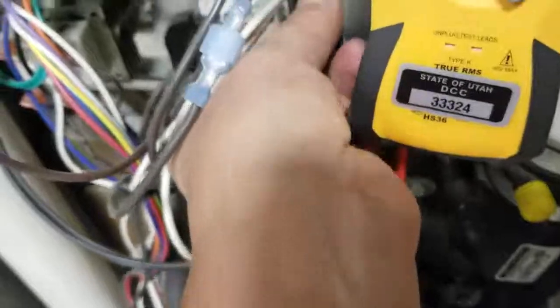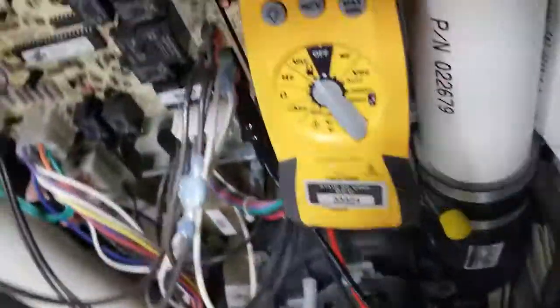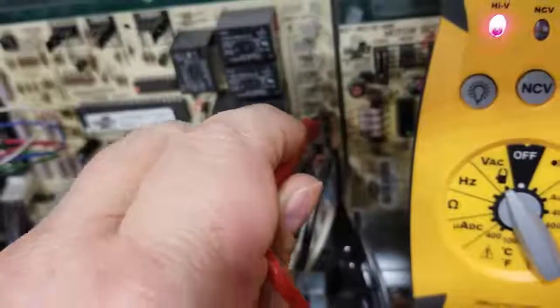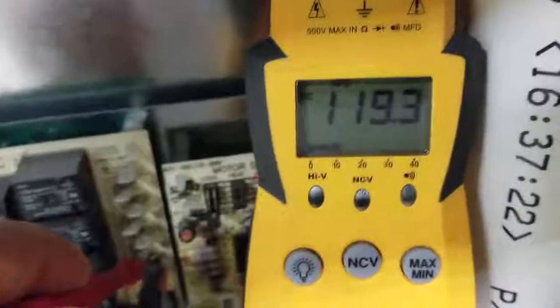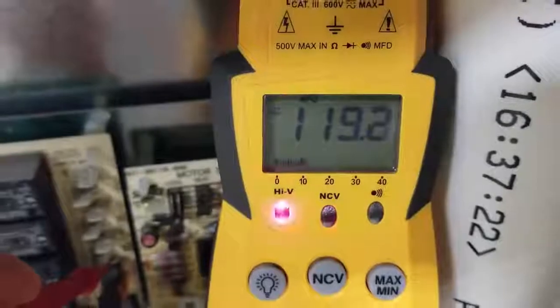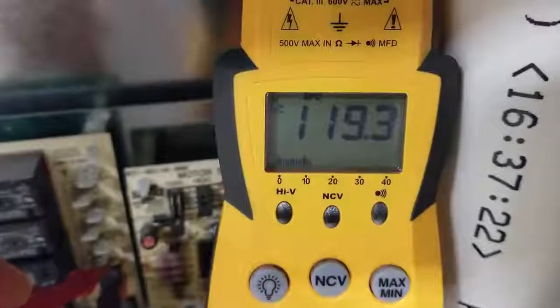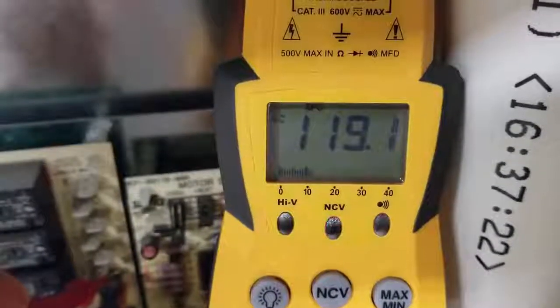So I'm going to go ahead and hook my alligator clip to a dedicated neutral, and then I'm going to put my probe on line. So right now I'm checking the main line voltage in. We should have somewhere around 120 volts.